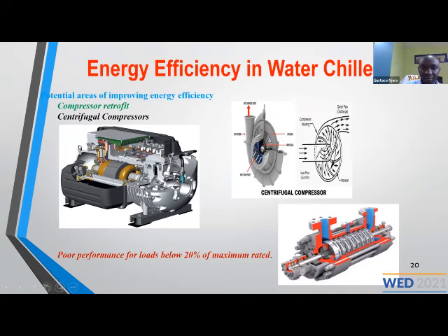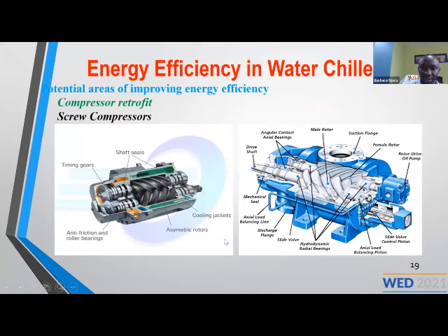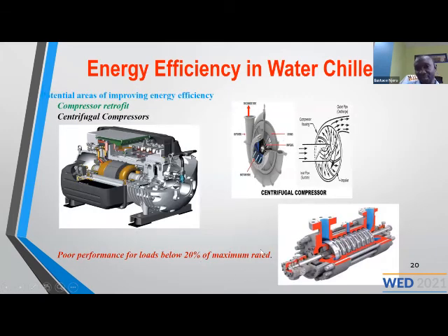If you move your system from screw to centrifugal, in most cases, from experience, you can save up to 20% at the maximum. As you have said, they are very poor when you operate them below 20% of their rated speed. So even if you are using a VFD, make sure that you don't go below 80%. You can only reduce the speed by 20%. Some people go on using a VFD which reduces the speed up to 50%, so you find you are reducing the speeds below 80% of the rated speed. It's better to have a system with two compressors, so that if the load goes to a situation where you have to reduce the speed below 80%, you can switch one off and use the other one.